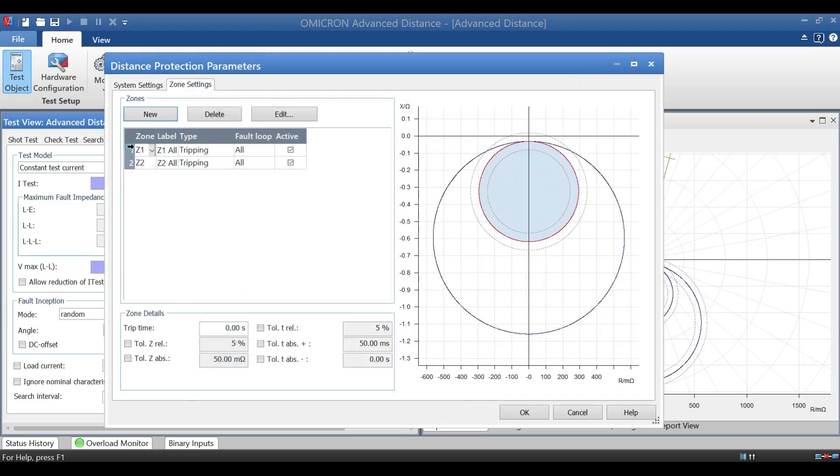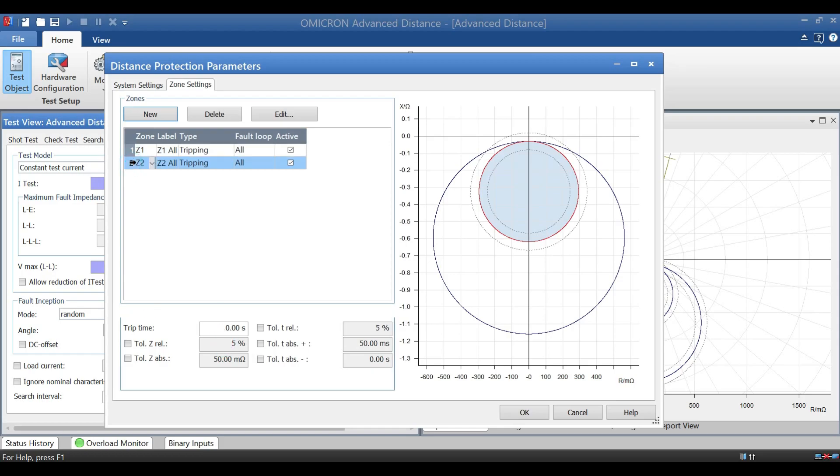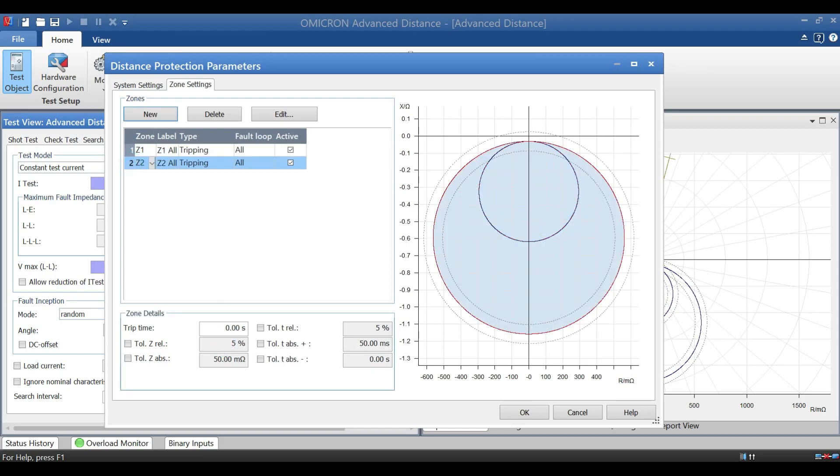Now we have to set trip time for zone 1 and zone 2. According to settings, the trip time is 0.1 second for zone 1 and zone 2 is 0.5 second. Once you finish all settings, you can select OK and come to main page.